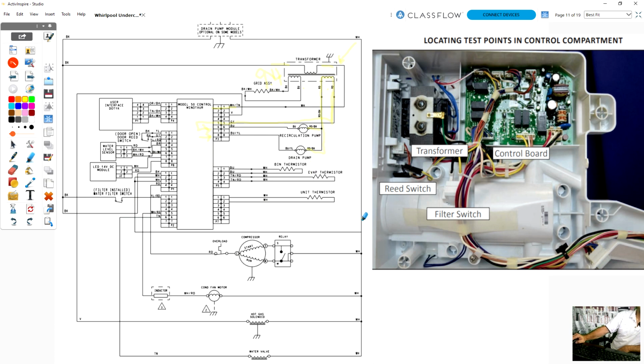Now, all the rest of the components that have neutral connected to them, the water valve, the hot gas, the condenser fan, the compressor, all of them are 120 volts if they connect to neutral. The thermistors are 5 volts. And all of these sensors and user interface are low voltage as well. Here it says the LED is 14 volts DC. So this might be a 14 volt output right here. And that's what's feeding the water level sensor, the module, and your 2 pumps.